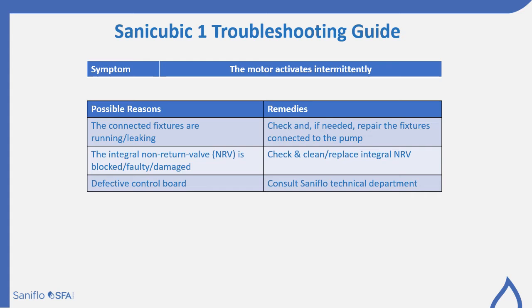The NRV could be blocked, faulty or damaged. This is keeping the water running back into the pump, making it activate without actually clearing anything. So clean and check the NRV, replace it if necessary. Once again, a defective control board may be your issue, and if that is the case, consult the Saniflo technical department.